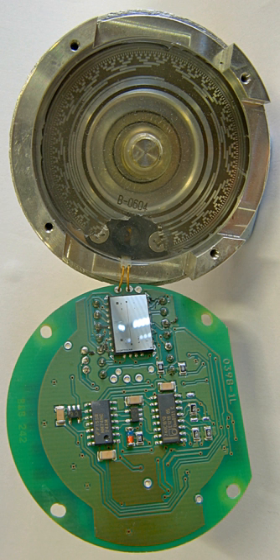Brushless motors require electronic commutation, which often is implemented in part by using rotor magnets as a low-resolution absolute encoder, typically 6 or 12 pulses per revolution. The resulting shaft angle information is conveyed to the servo drive to enable it to energize the proper stator winding at any moment in time.